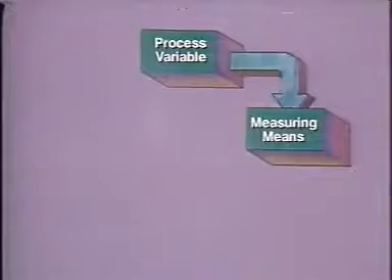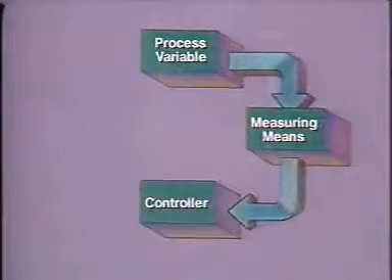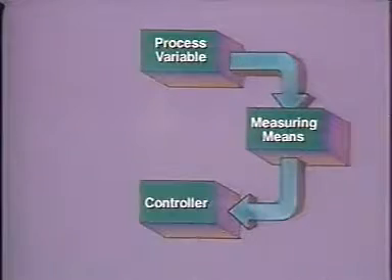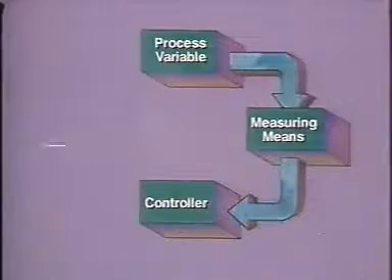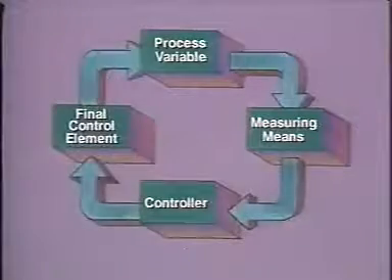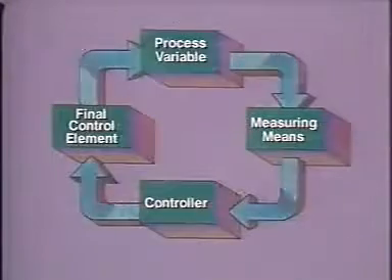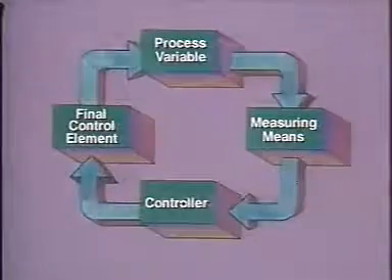In any control situation, four things are necessary. First, there is a process variable that needs measurement and control. For each process variable, there is a measuring means — one or more instruments that can measure the process variable. There must be some kind of control mechanism to receive the measurement information and determine how it compares with the desired value or set point, and also tell the valve what action, if any, it should take. And there is a final control element, which is usually a valve. The final control element makes the actual process change that keeps the process variable at set point. These four elements are called a control loop.